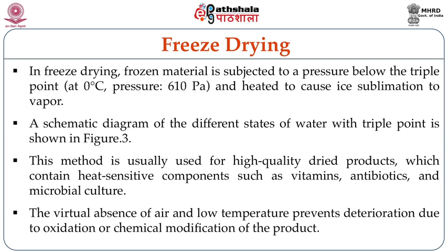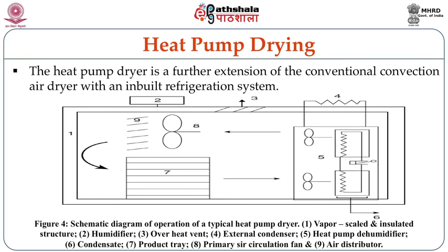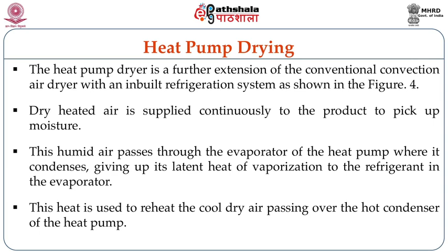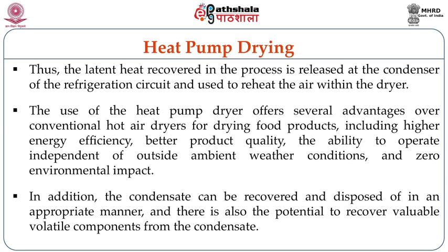Then we have the heat pump drying. As you can see from figure 4, heat pump dryer is a further extension of conventional air dryer with an inbuilt refrigeration system. Dried heated air is supplied continuously to the product to pick up moisture, and the humid air passes through the evaporator of the heat pump where it condenses, giving up its latent heat of evaporation to the refrigerant in the evaporator. This heat is used to reheat the cool dry air passing over the hot condenser of the heat pump. Thus, the latent heat recovered in the process is released at the condenser of the refrigeration circuit and used to reheat the air within the dryer.